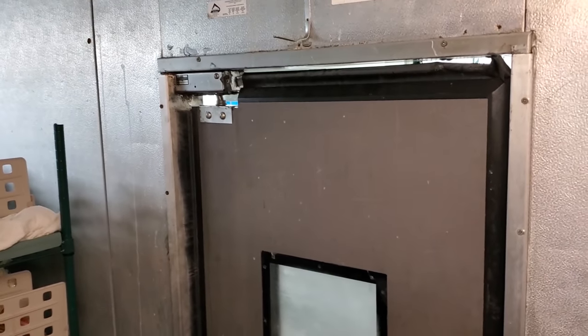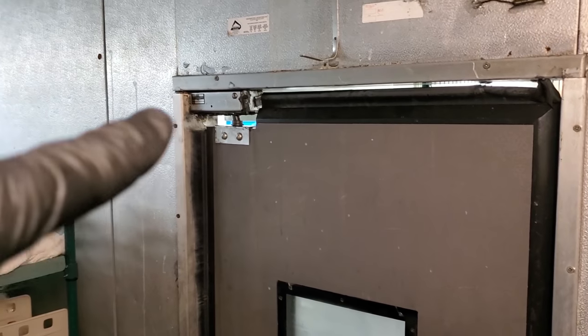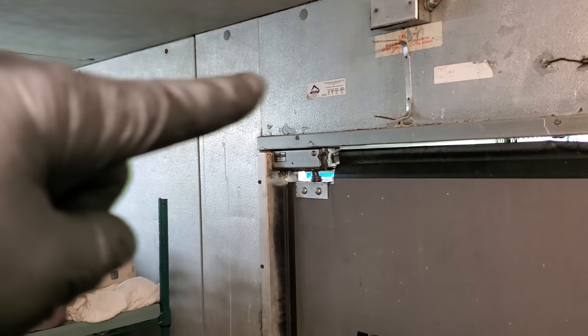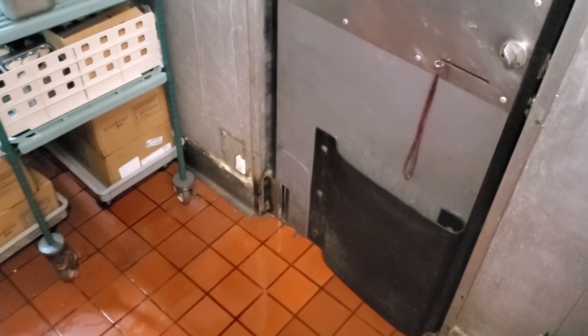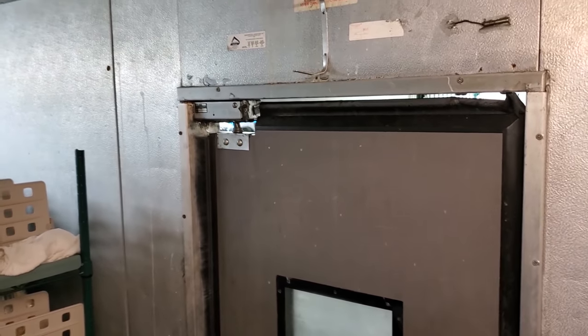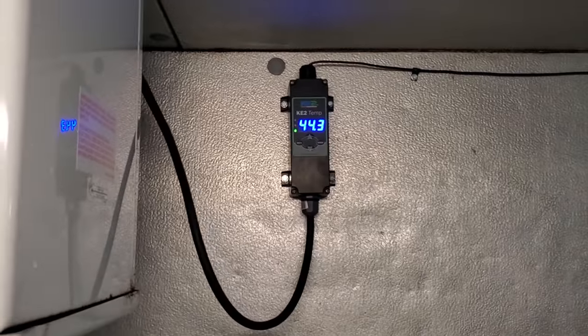Supposedly last week the door was broken — it had been off for several days. They were propping it up or something, then had a welder come in and weld that pin, but the pin's in there crooked. I really don't want to take the door apart because it's functioning at the moment and I'm afraid if I take it apart it's going to fall apart. I'm going to find out if I can get a new saddle bracket, a new upper mechanism with all the parts, a new bottom pin, and a new bushing down in the bottom. I've done these doors a bunch, but normally the customer would just replace the whole door assembly. With this whole virus going on, they're not trying to spend a lot of money. We'll definitely need to turn the defrosts back down when we're done though, because eight defrosts is way too many for this unit.